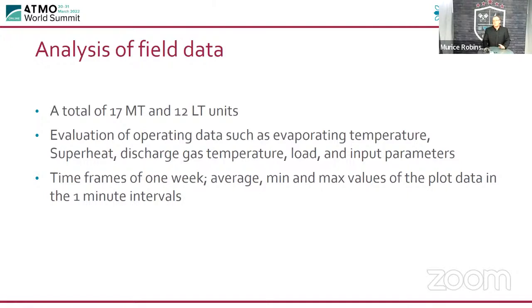So what we did is we compared the saturated suction temperature, we checked the superheat, the loads, the parameters. We had a look at all of the data, and we took a time frame of 1 week, the average of the minimum and maximum. And then we plotted that data in 1 minute intervals, and we had a look to see where everything was. And then we took the average of the whole thing.